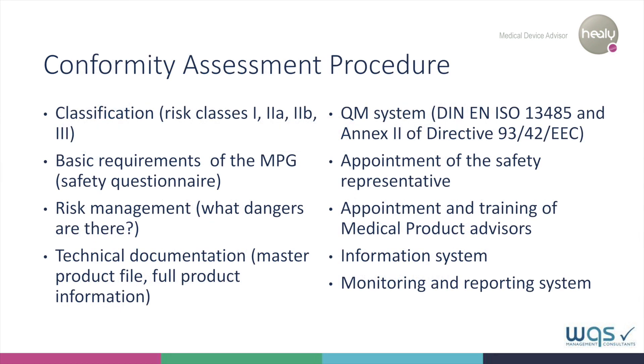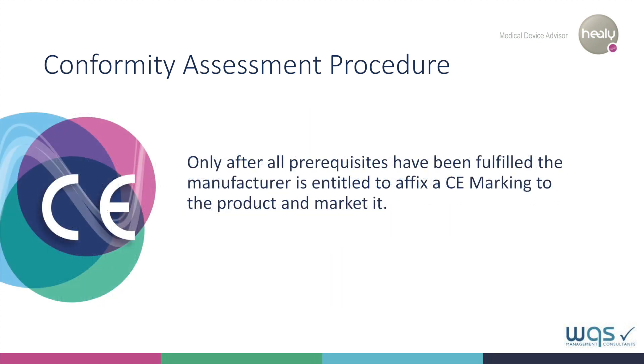Let's now move on to the so-called conformity assessment procedure. In order to carry the CE mark, manufacturers and their products must meet a number of strict requirements. These include classification into one of the risk classes, compliance with all requirements of the Medical Devices Act, proof of a risk management policy, and detailed technical documentation of the product. Additionally, a quality management system in accordance with the relevant standards must be implemented. A safety representative and MDAs must be appointed and trained. An information, monitoring and reporting system that complies with the relevant regulations must be implemented. Only if all these measures are in place is the manufacturer allowed to affix a CE mark to its products.